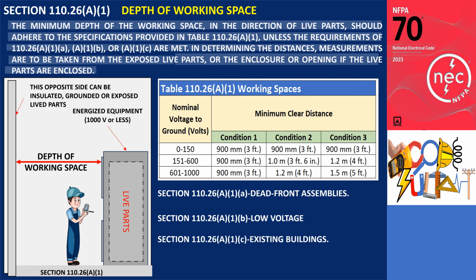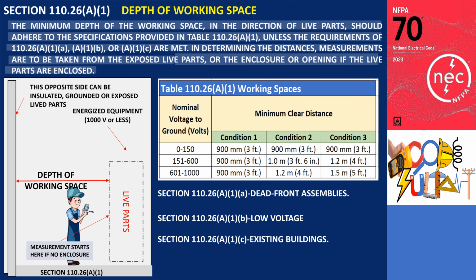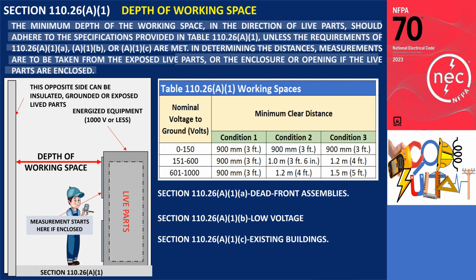The issue of where to begin the measurement often arises, with questions such as whether it should start from the live parts, the dead front, or the cover. The NEC clarifies that the measurement should commence from the exposed live parts unless they are enclosed. In the case of enclosed live parts, the measurement should commence from the enclosure or opening.